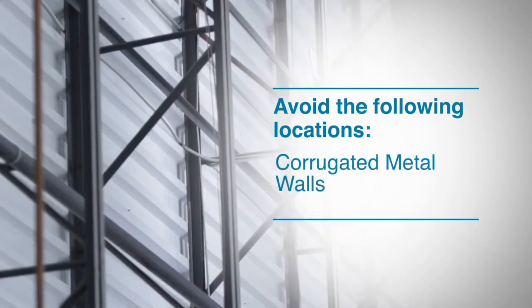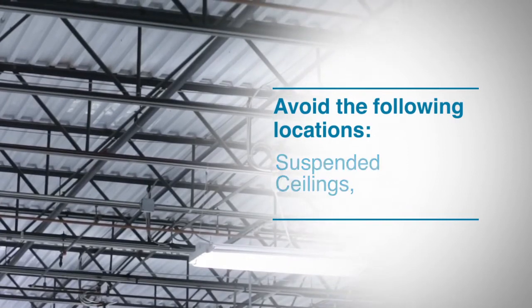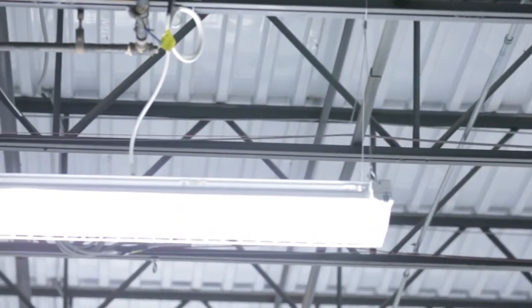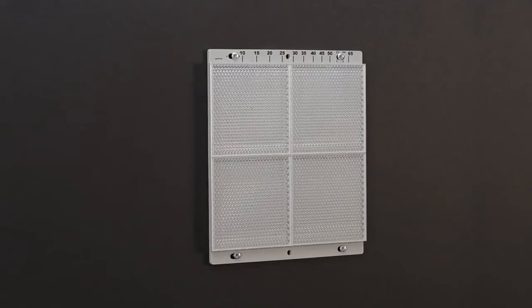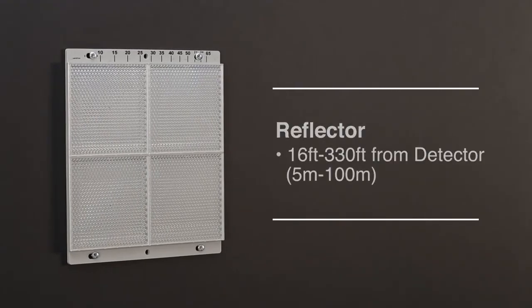Avoid mounting the beam on corrugated metal walls, external building sheathing, suspended ceilings, and steel web trusses, as these surfaces tend to shift with temperature or humidity changes. The reflector needs to be mounted anywhere from 16 to 330 feet from the detector.